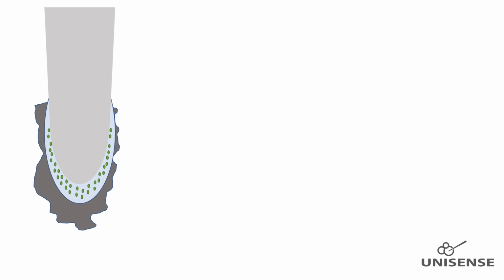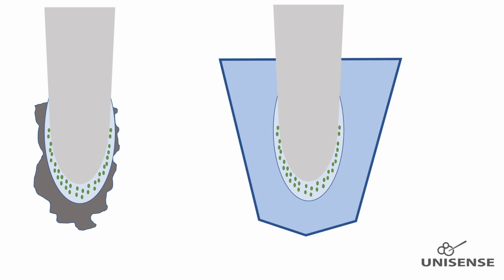If the Optode tip gets biofouled or covered with sticky polymers, it might measure incorrectly. The Optode tip tolerates almost all possible cleaning substances like alcohols, acids, detergents, proteinase solutions, etc. So it is recommended to insert the Optode in different cleaning substances to see if it solves the problem as the first attempt to remove the fouling. Do not use organic solvents which will dissolve the polystyrene matrix.